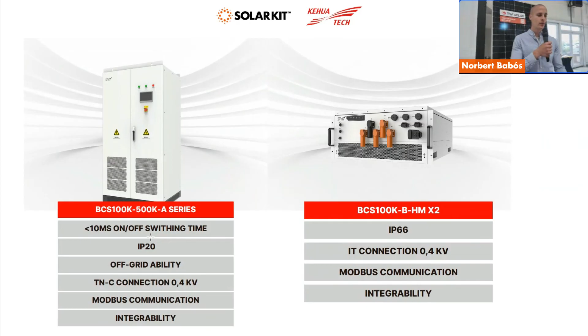These are the bundles that you can put together. If you're thinking about cabinet solutions, it's going to be either the modular 100 kilowatt PCS or the transformer-included 100 to 500 kilowatt PCS, because these can be implemented in small scale solutions. If you'd like to go for large scale solutions, above 4 megawatt hour capacity, then it's going to be the container size solution with the container size PCS.